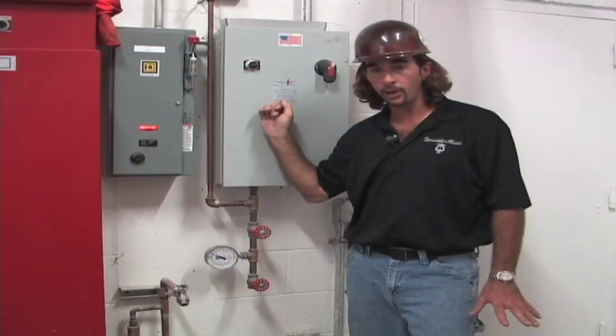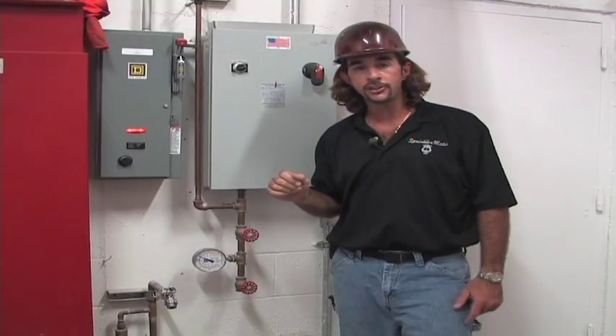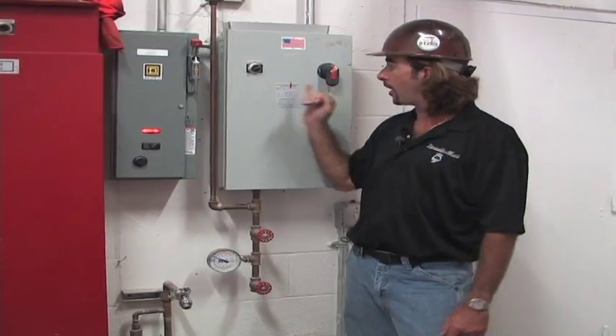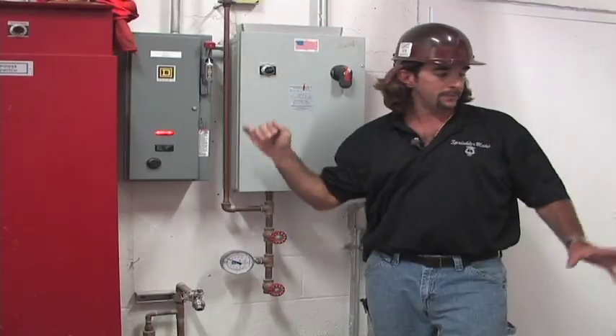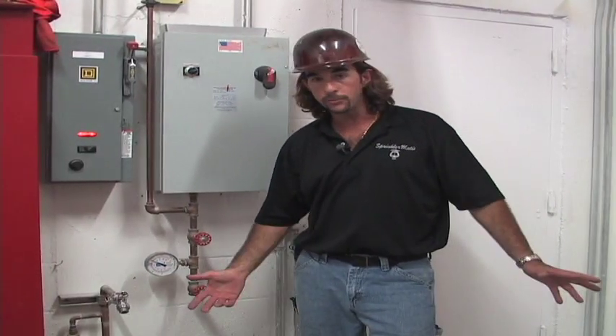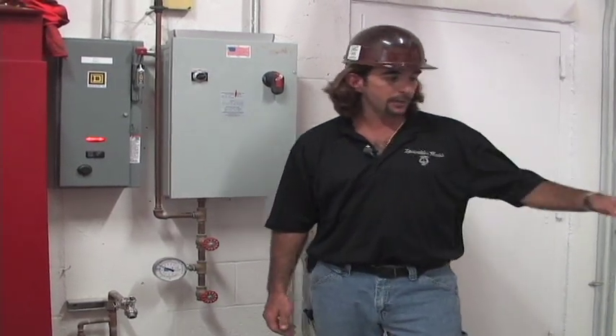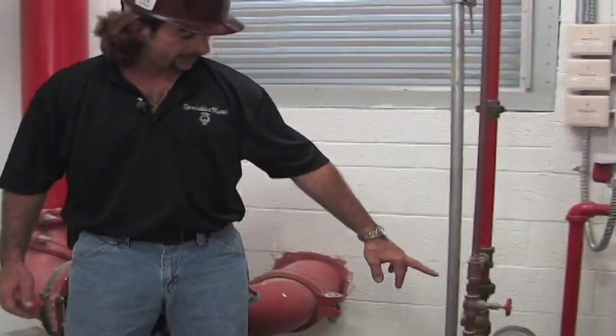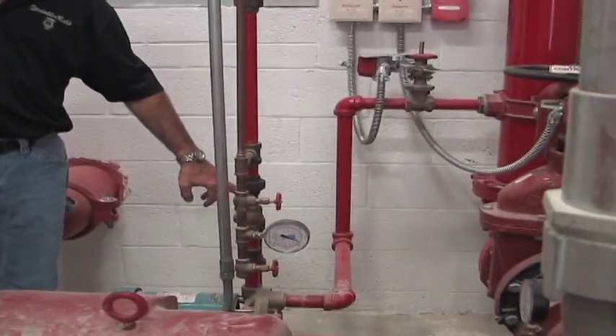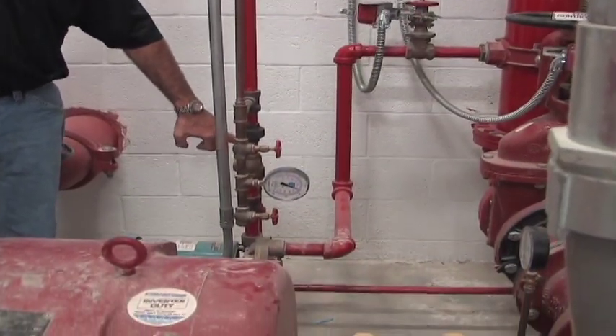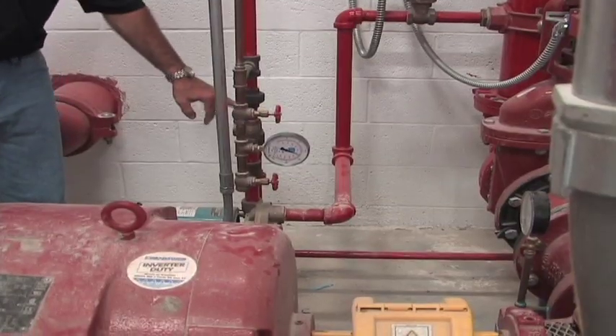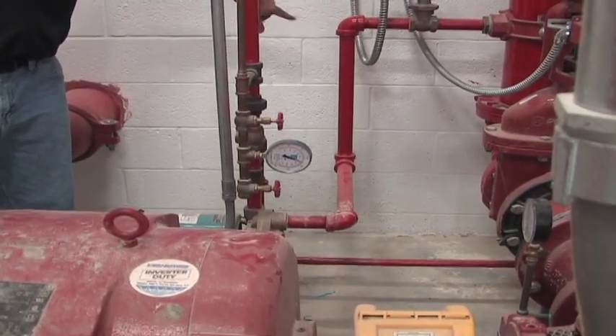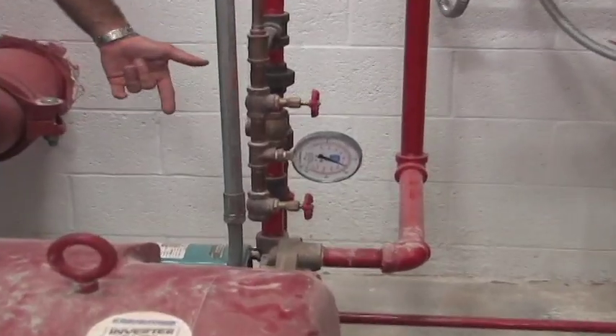As far as maintenance goes, there really is no maintenance on the jockey pump, just to make sure that it stays on and the selector switch is in auto. The bearings and everything are permanently greased. There is no lubrication or adjustments that it needs. Also, like on the fire pump, the jockey pump has a relief valve. If for some reason somebody had turned it to the hand position and the pressure got up over a certain pressure, this valve would open up and discharge water automatically and shut off when the pressure went back down.